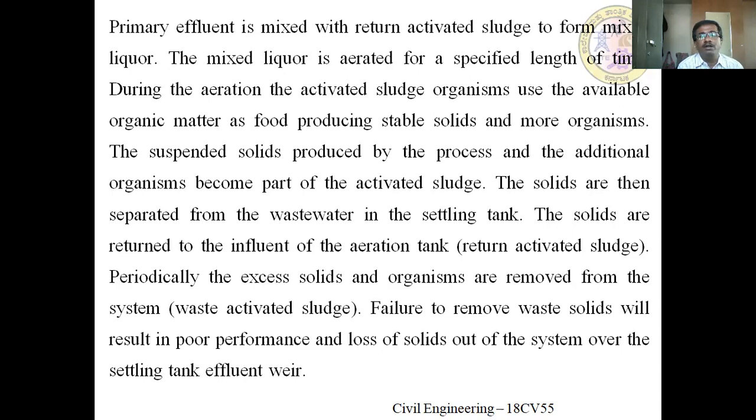Periodically, the excess solids and organisms are removed from the system. Failure to remove waste solids will result in poor performance and loss of solids out of the system over the settling tank effluent weir. That means we must timely remove the excess sludge produced. If you do not remove the excess waste solids, which include dead microorganism cells, organic matter, inorganic and inert materials, it affects the efficiency of the treatment unit.